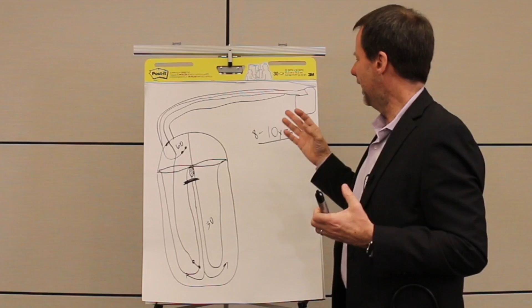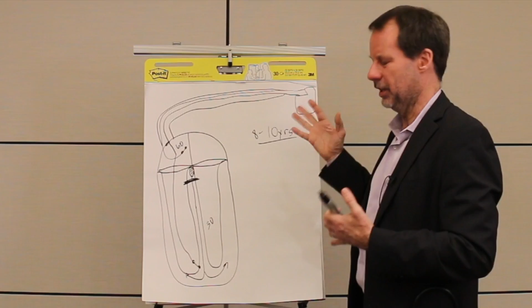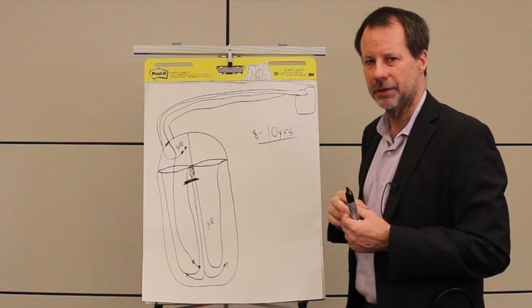Wires can also break. These things are in the body, essentially doing the paperclip thing, flexing back and forth, especially up here in the arm where people move, and over time the wires can break—maybe 1 in every 100 after about 5 years. If a wire breaks, it may malfunction or shut down completely. More often it sends interference or electrical static that we can pick up in the device, and then we can address it before anything bad happens. So that's a rare complication of pacemaker systems, but one we can also deal with.